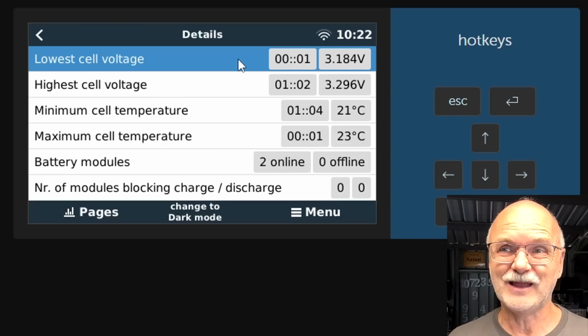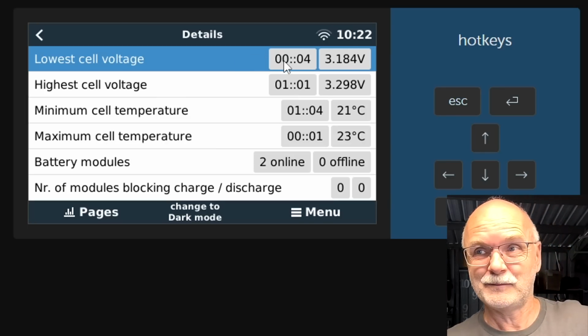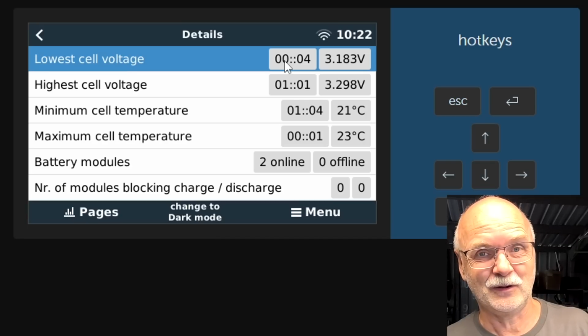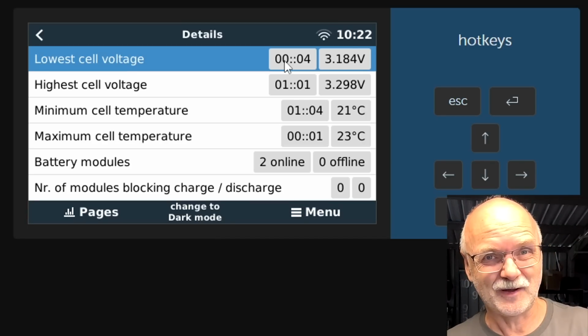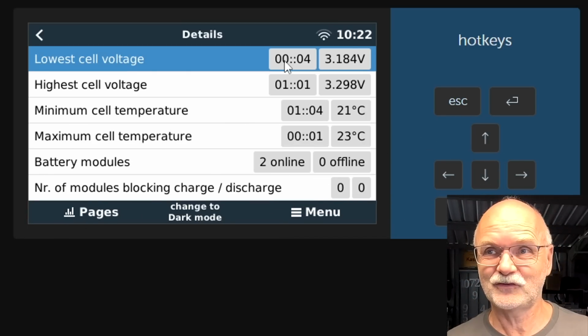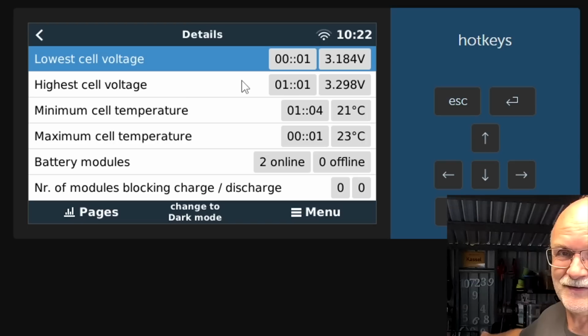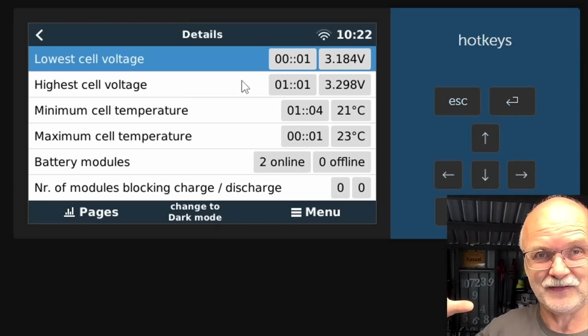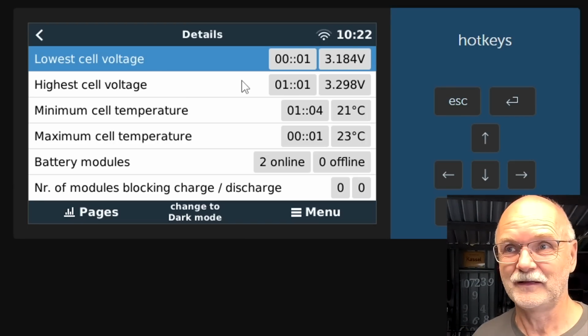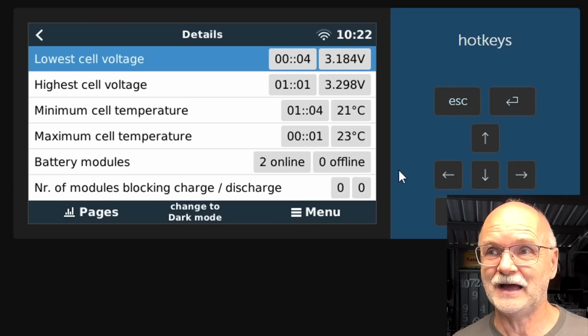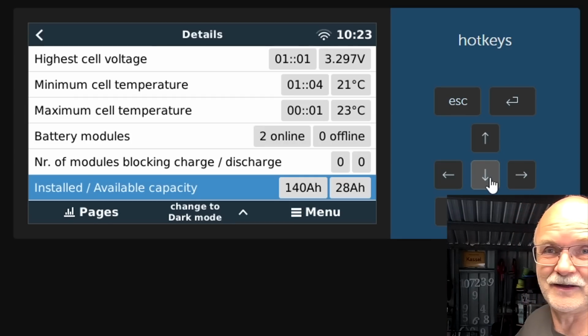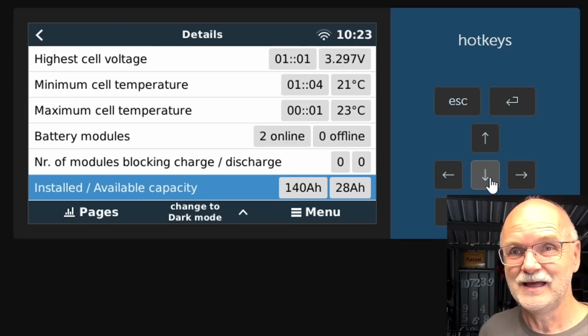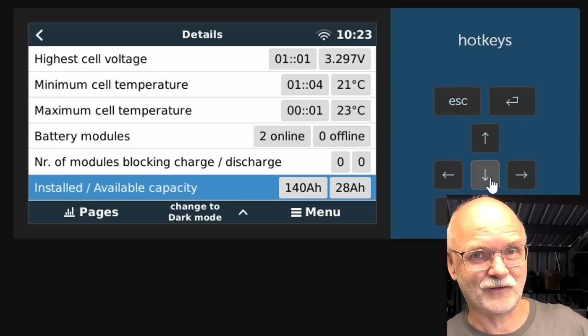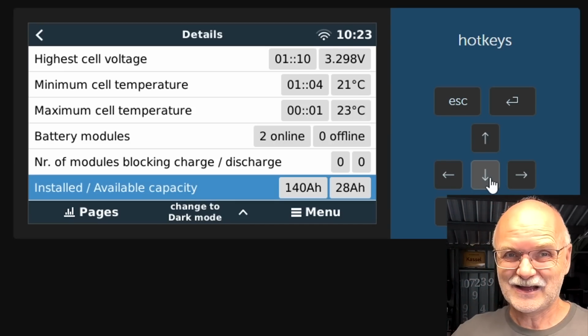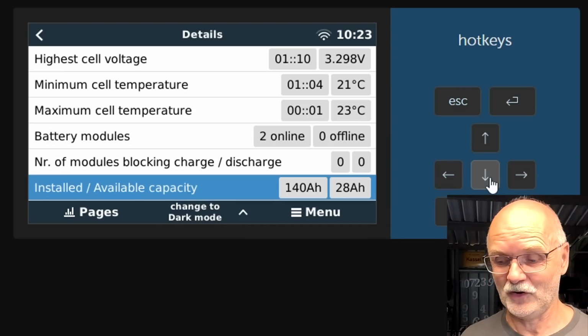So you can now see the lowest cell is in battery number 0, our test battery here on the bench where the master B-series BMS is connected, and the highest voltage is in the JK battery controlled by the JK inverter BMS. We've got 2 batteries online, and combined we have 100 ampere hours from the JK battery plus another 40 ampere hours from this test battery, combined reported to the inverter.